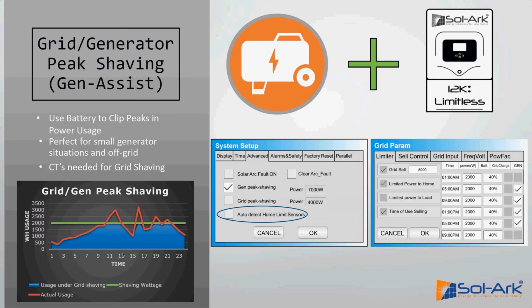So you're going to save a lot of money for your customer there if they're getting billed that way. Quick note too, if you're doing grid peak shaving, you are going to need to install the current transformers for that. The Sol-Ark ships with current transformers already in the box that are rated for 2-gauge wire. If you know that your install is going to require larger CTs because you've got like a 4-gauge wire for the main service panel or something like that, please let us know whenever you order, and we can get those to you. I think they're like $80 or something like that. Just make sure to let us know.